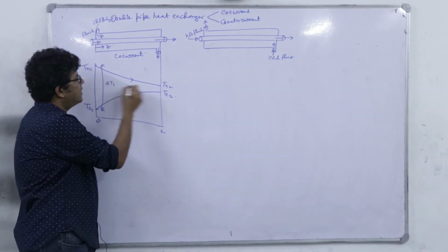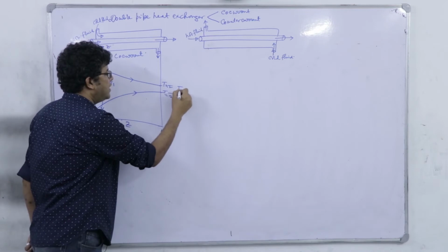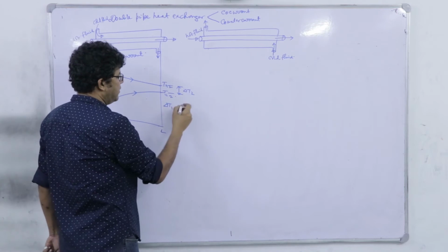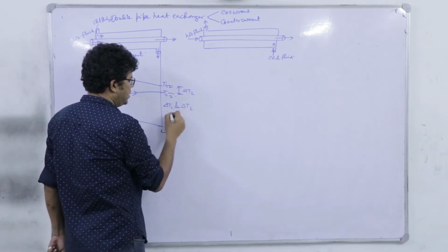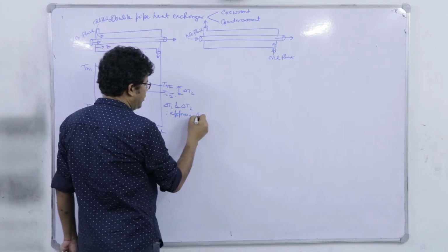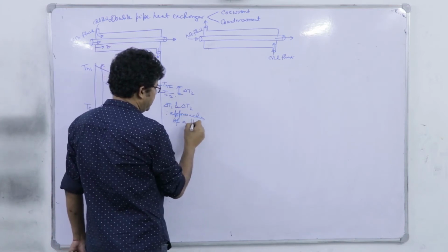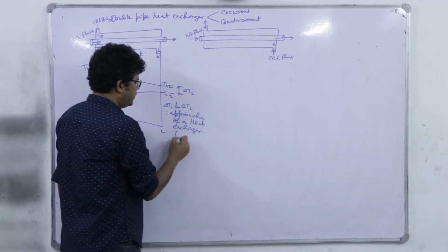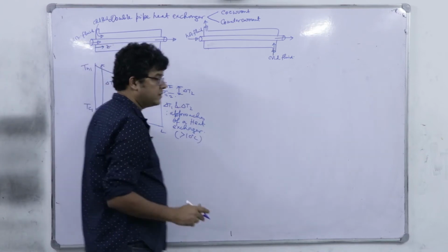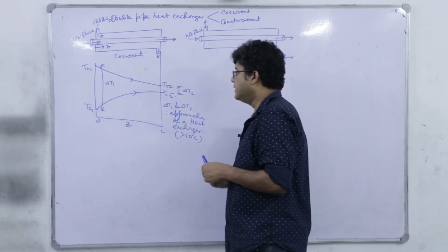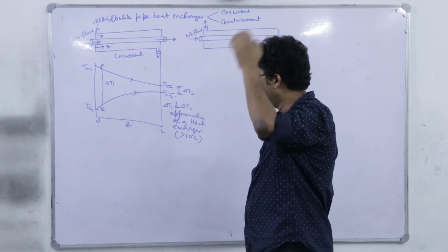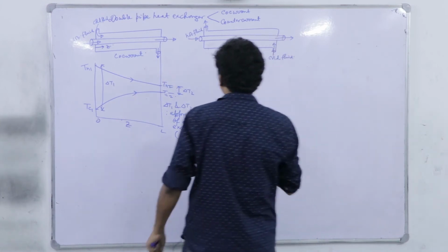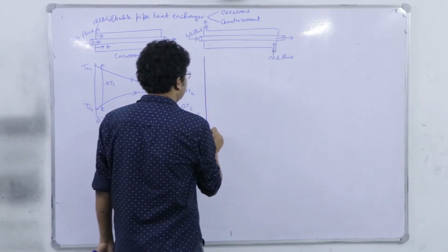that is delta T1 and delta T2, delta T1 and delta T2, they are approach or approaches of a heat exchanger, right. So, generally should be greater than 10 degrees Celsius. It is a standard thumb rule that in design we have to keep in mind that we have to go for maintaining that approach around 10 degrees Celsius. Whereas in counter current, you see what happens.